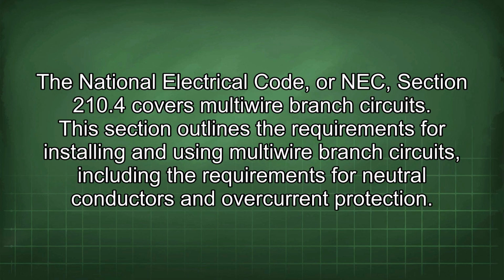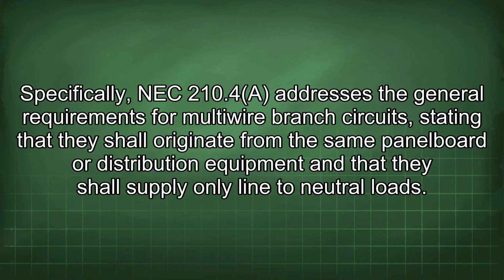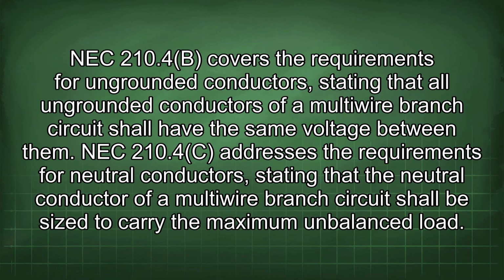The National Electrical Code, or NEC, Section 210.4 covers multi-wire branch circuits. This section outlines the requirements for installing and using multi-wire branch circuits, including the requirements for neutral conductors and overcurrent protection. Specifically, NEC 210.4(A) addresses the general requirements for multi-wire branch circuits, stating that they shall originate from the same panel board or distribution equipment and that they shall supply only line to neutral loads. NEC 210.4b covers the requirements for ungrounded conductors, stating that all ungrounded conductors of a multi-wire branch circuit shall have the same voltage between them.